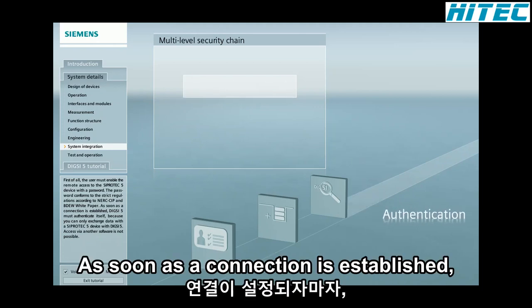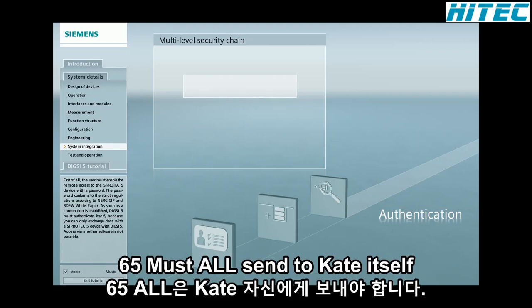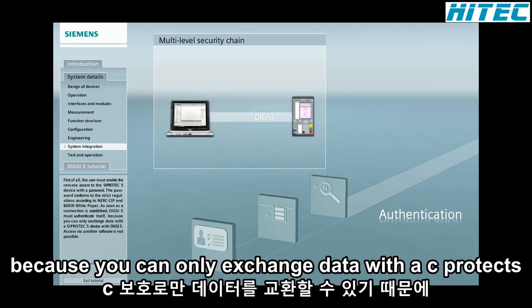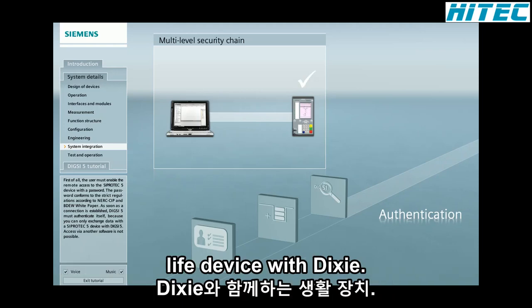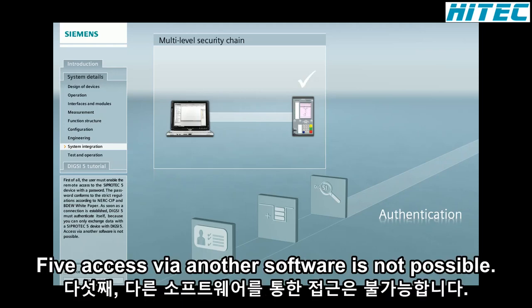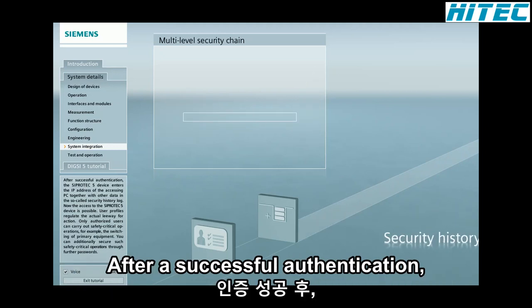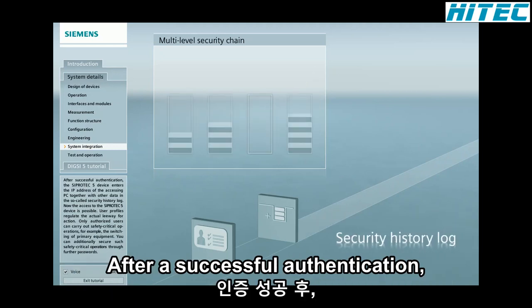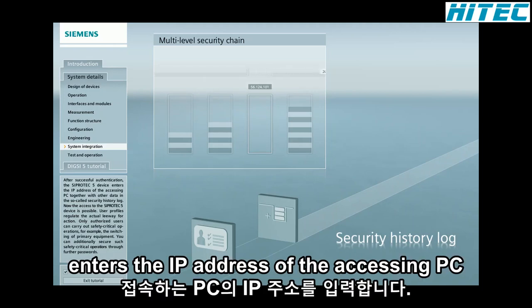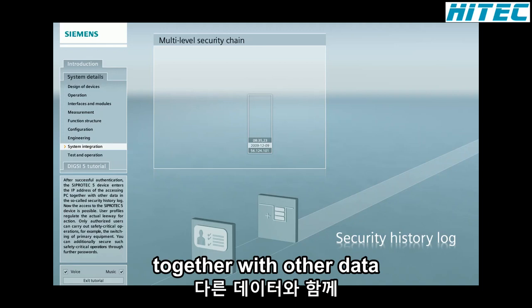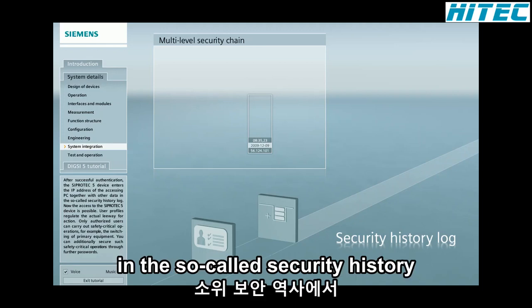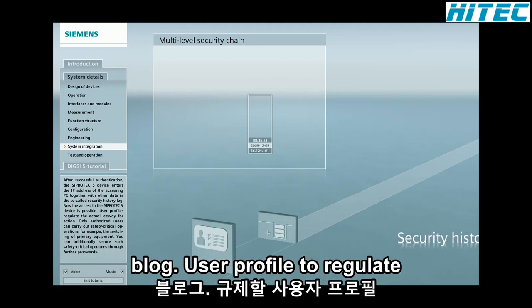As soon as a connection is established, DIGSI 5 must authenticate itself because you can only exchange data with a SIPROTEC 5 device with DIGSI 5. Access via another software is not possible. After successful authentication, the SIPROTEC 5 device enters the IP address of the accessing PC together with other data in the so-called security history log.